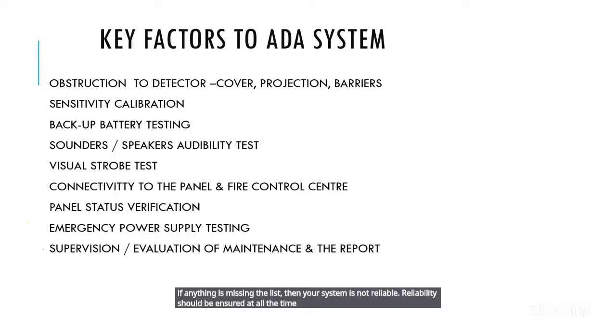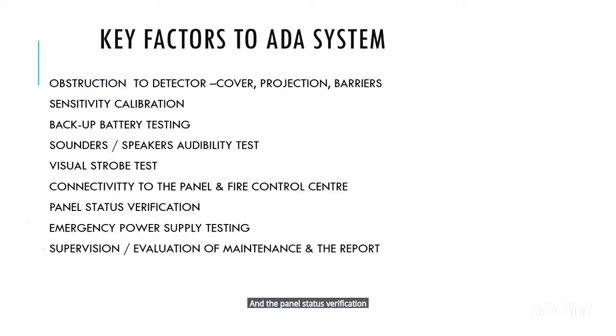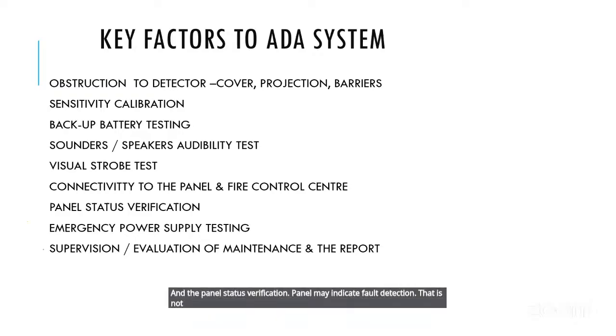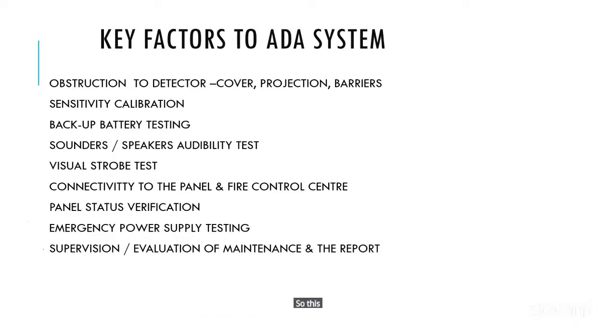And the panel status verification. The panel may indicate fault detection, and that is not recorded at all. When I asked what the fault was, he said it has been there for 3 months, sir. That is no problem, sir. The panel is working, the detectors are working. So this is the way we understood the panel and the detector system.